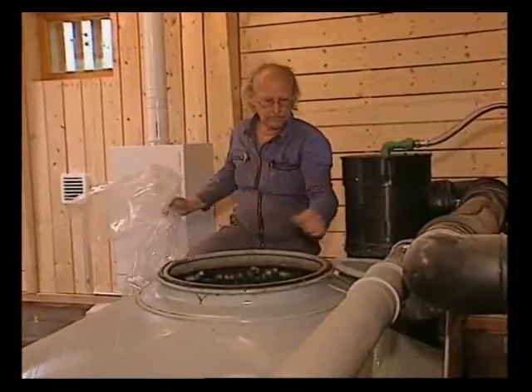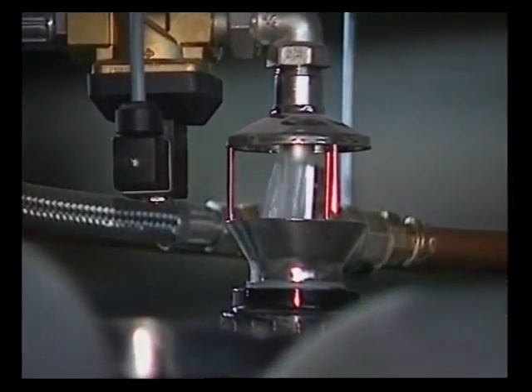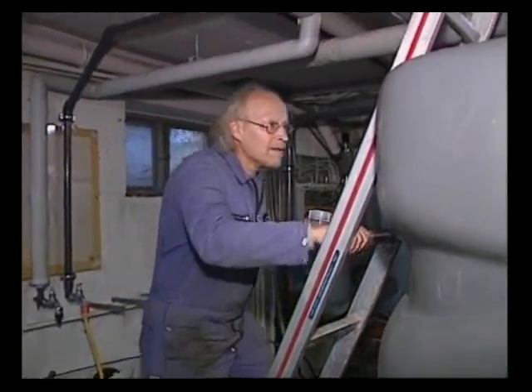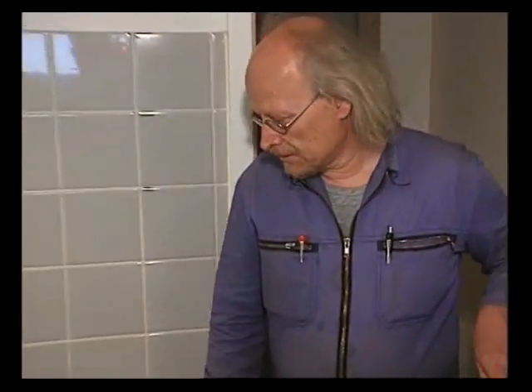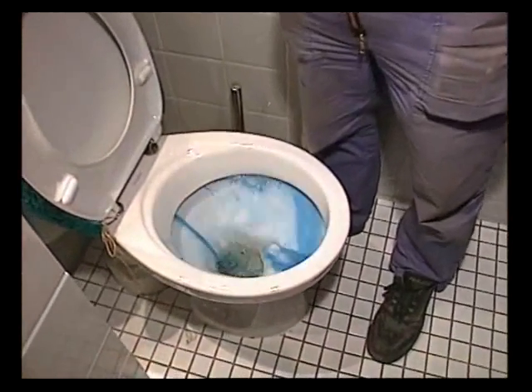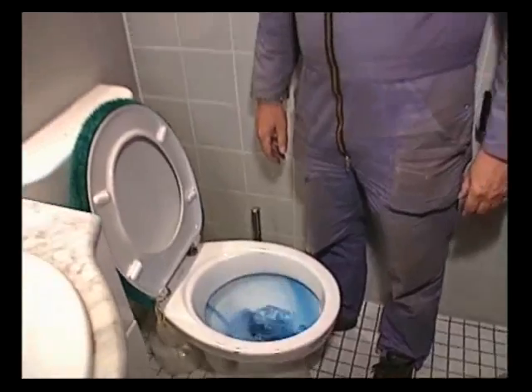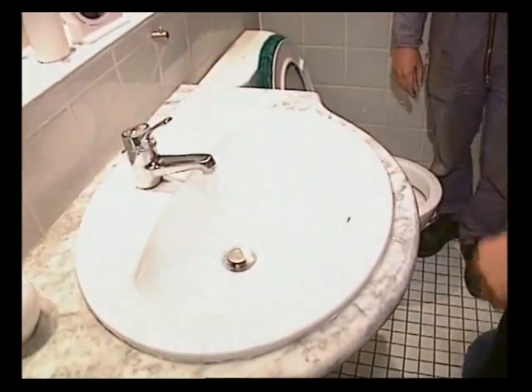A very promising research project initiated by scientists and industry, whereby bacteria which settle on these foam cubes can proliferate vigorously. A back-up system may supply drinking water or rainwater through a separate network to cover demand when needed. I am going to add some food dye to our service water tank in order to test the pipe network systems and exclude any cross-connections. I flush and here the right water comes out — this is our service water. Now we move to the wash basin, where no blue water should come out, neither on the warm nor on the cold tap side.